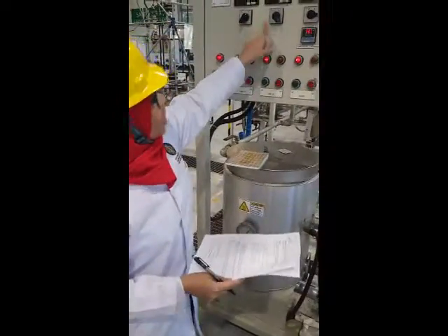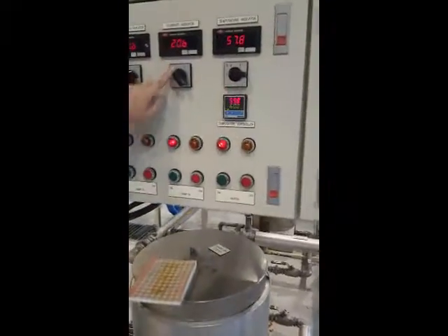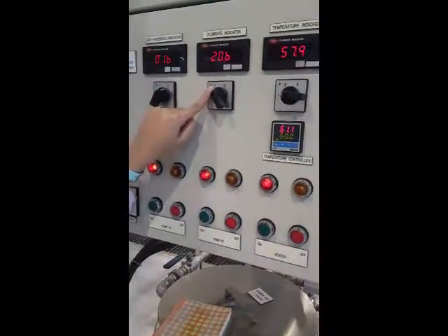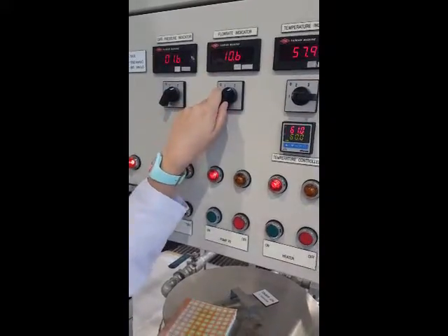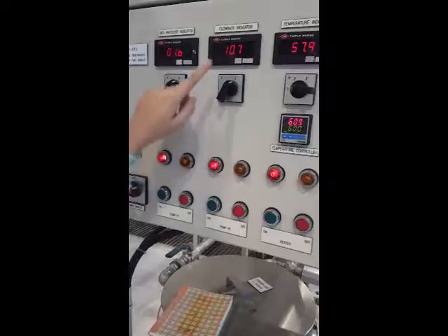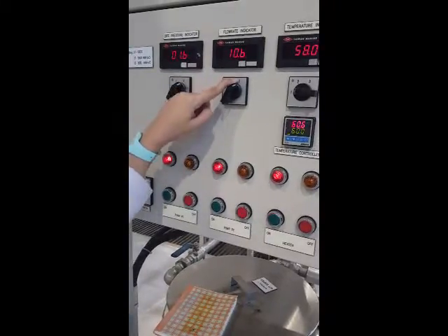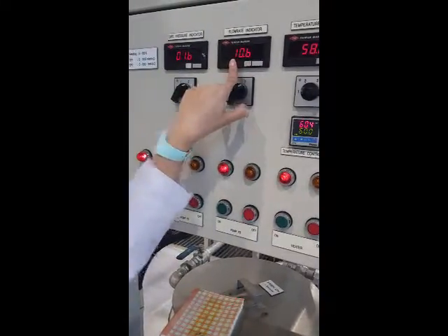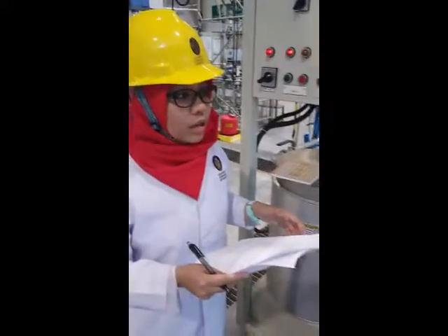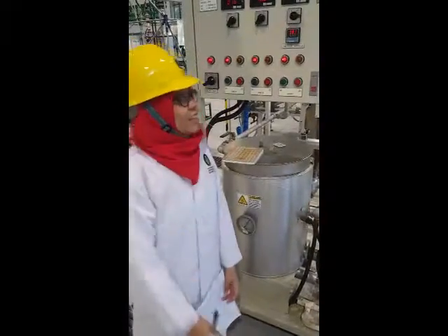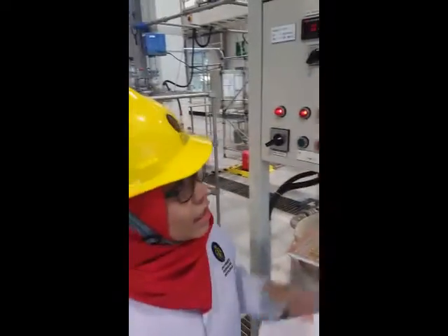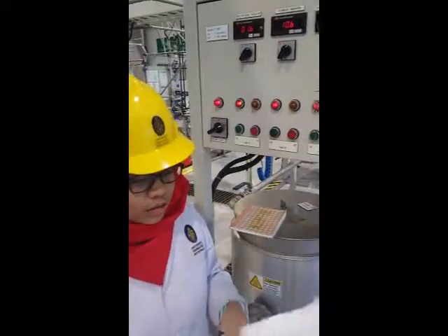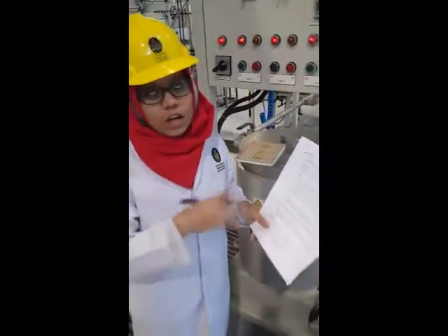So once we've determined the flow rate, we check it here. Number 1 states that it's for hot water, so it shows that it's at 20. And 2 is for cold water, and this shows that it's at 10. Correction, this reading is liter per minute. So that is how you know the flow rate for the hot and cold.